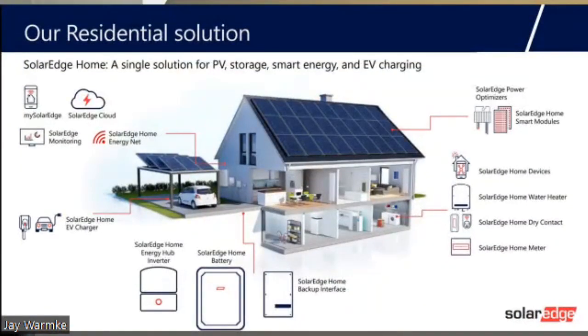All right, so what does a SolarEdge system look like for those of you who are not familiar with the overall system? As a little bit of background, the concept of microinverters came around before, but it really came into the forefront when the rapid shutdown provision of the National Electrical Code came into play, where they said, okay, we need you to shut off the power at the panel. And the industry was kind of flummoxed as to how exactly to do that, because the wire going from the panel to the inverter was still live during sunlight.